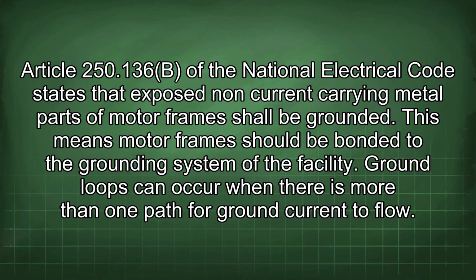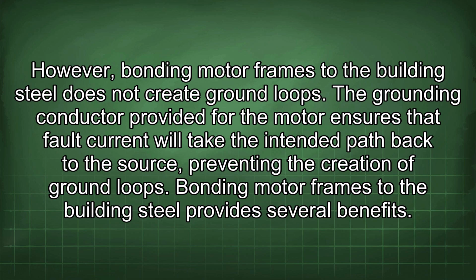Article 250.136(B) of the National Electrical Code states that exposed non-current carrying metal parts of motor frames shall be grounded. This means motor frames should be bonded to the grounding system of the facility. Ground loops can occur when there is more than one path for ground current to flow. However, bonding motor frames to the building steel does not create ground loops.